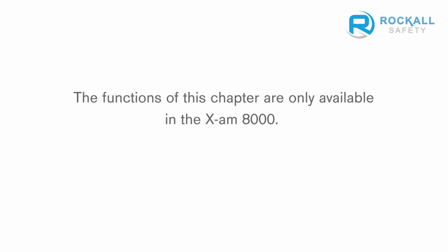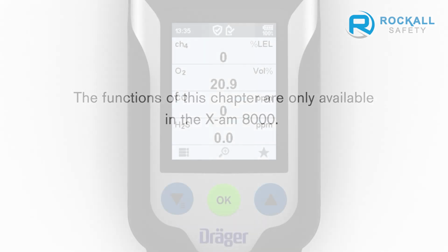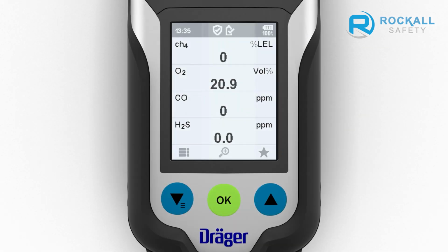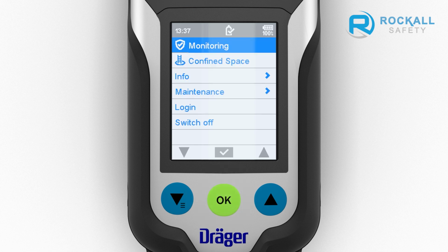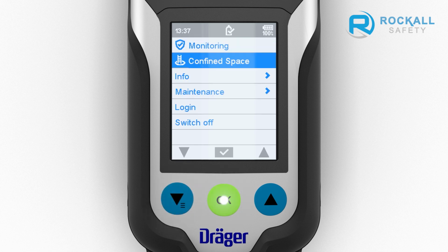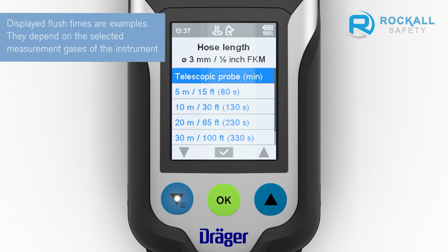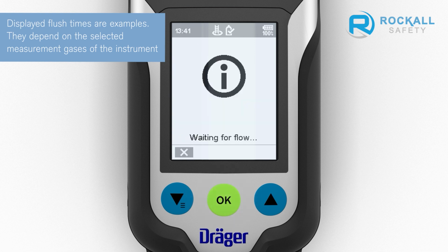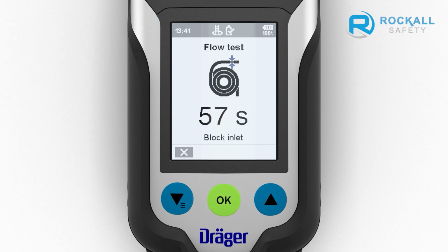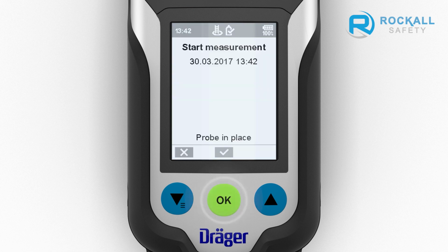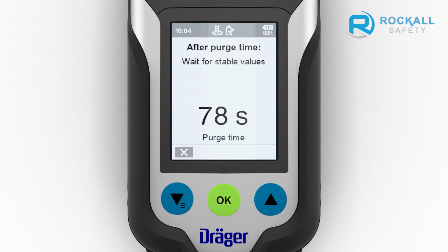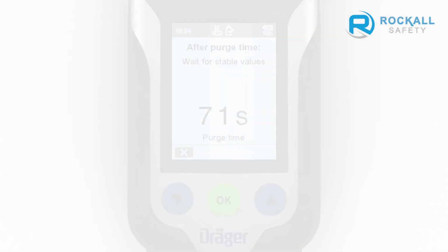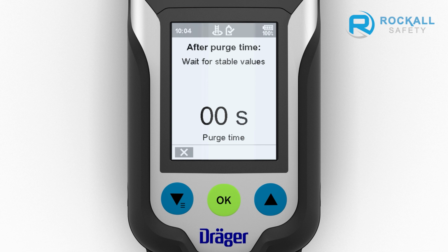The functions of this chapter are only available in the X-am 8000. The Dräger X-am 8000 provides a measurement wizard for carrying out the measurements in confined spaces. Open the menu in measuring mode and select the confined space option. This function can be configured to appear before or after the password. Then follow the prompts given by the wizard. The calculated flooding time shows the minimum waiting time required to route gas from the sampling point to the sensors.